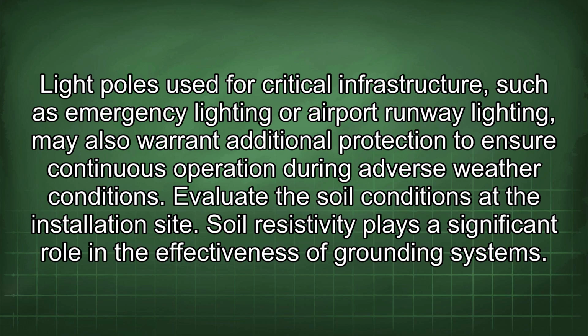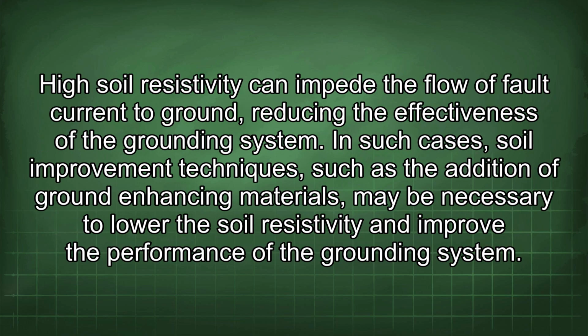Evaluate the soil conditions at the installation site. Soil resistivity plays a significant role in the effectiveness of grounding systems. High soil resistivity can impede the flow of fault current to ground, reducing the effectiveness of the grounding system. In such cases, soil improvement techniques, such as the addition of ground-enhancing materials, may be necessary to lower the soil resistivity and improve the performance of the grounding system.